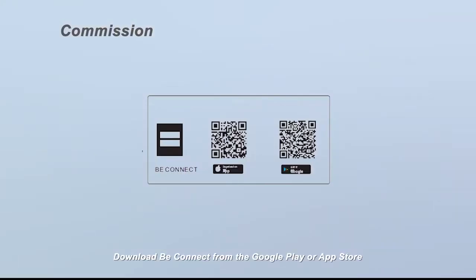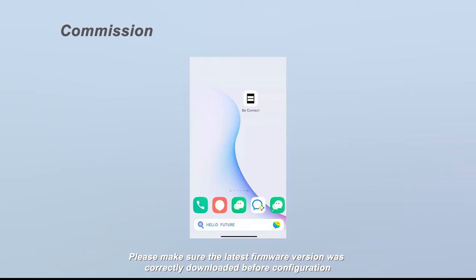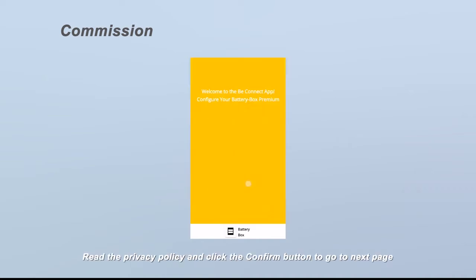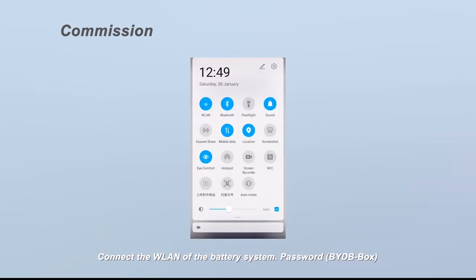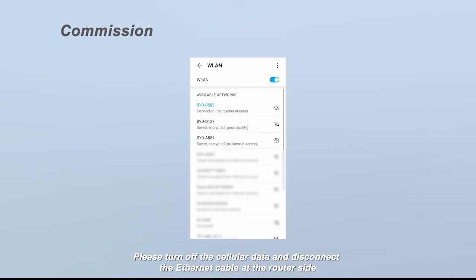Download Be Connect from the Google Play or App Store. The battery system requires the latest firmware version; please make sure the latest firmware version was correctly downloaded before configuration. Authorize Be Connect and choose the language — six languages are available: English, Chinese, German, Spanish, French, and Italian. Read the privacy policy and click confirm, then click the download firmware button. Connect to the WLAN of the battery system; password: BYDB-Box. Please turn off the cellular data and disconnect the ethernet cable at the router side to improve the WLAN connection.